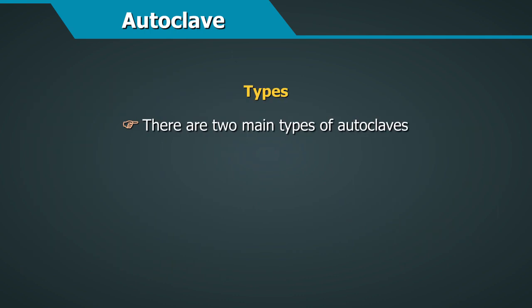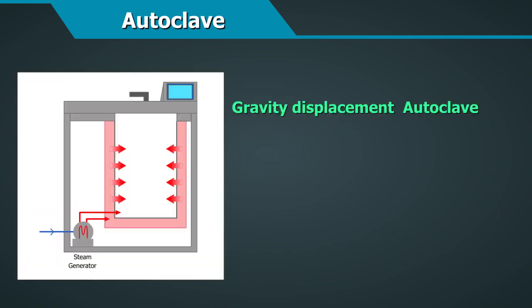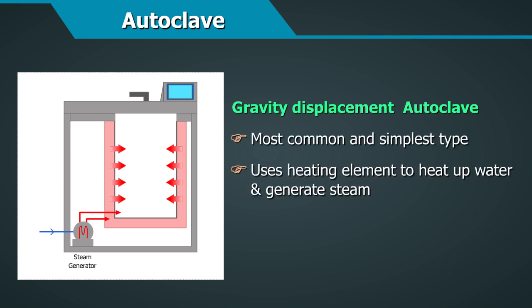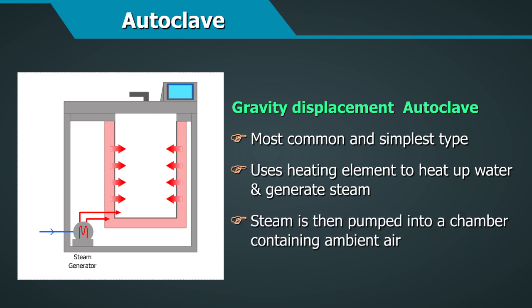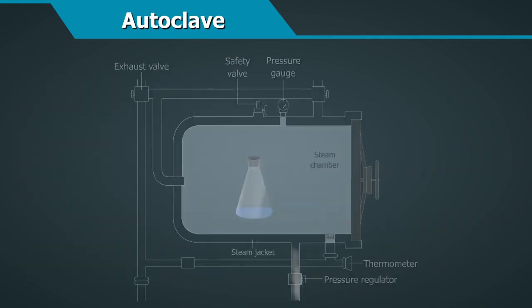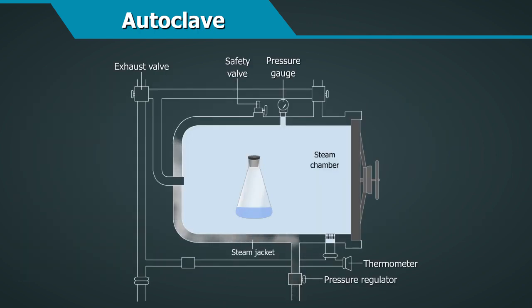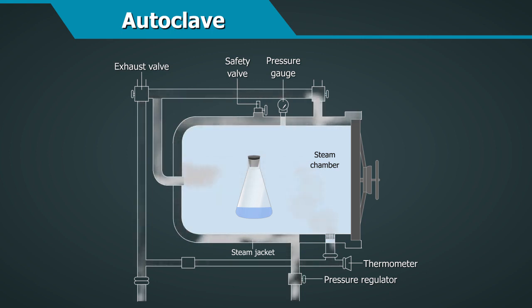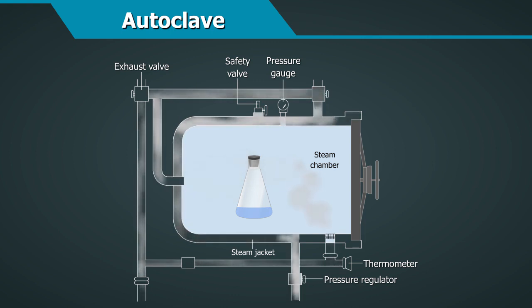Types. There are two main types of autoclaves. Gravity displacement autoclave. This is the most common and simplest type. It uses the heating element to heat up the water and to generate steam. The steam is then pumped into a chamber containing ambient air. Due to lower density, it rises to the top of the chamber and gradually displaces all ambient air, which is forced out through a vent below. The steam continues to be pumped at a higher pressure than normal atmospheric pressure, so it reaches a temperature of about 121 to 140 degrees centigrade. After the cycle, the steam is discharged through the exhaust valve.